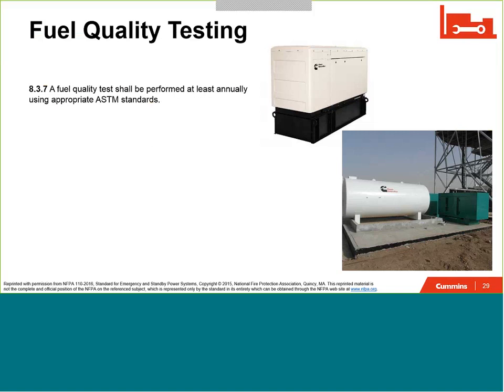I'll also talk here briefly about fuel testing. This is another very important testing requirement that we see on site and during the maintenance program. NFPA 110, as of today, has very little language about this. It simply states that a fuel quality test shall be performed at least annually using appropriate ASTM standards. Most manufacturers would agree with at least annually being sufficient. However, depending on the size of your fuel system on site, additional testing, whether that's twice a year or even quarterly, may be appropriate. We see this especially for larger facilities.